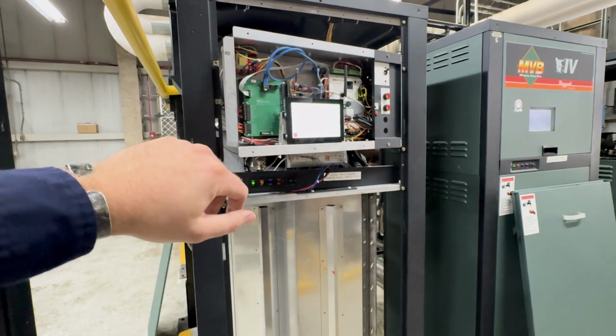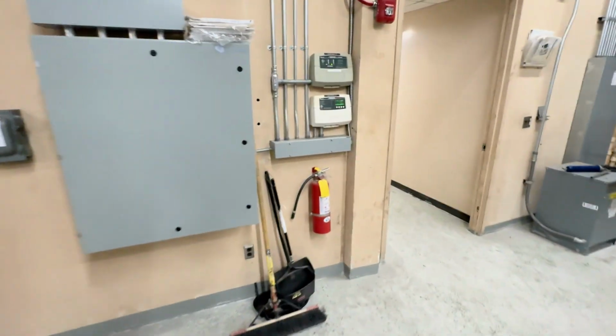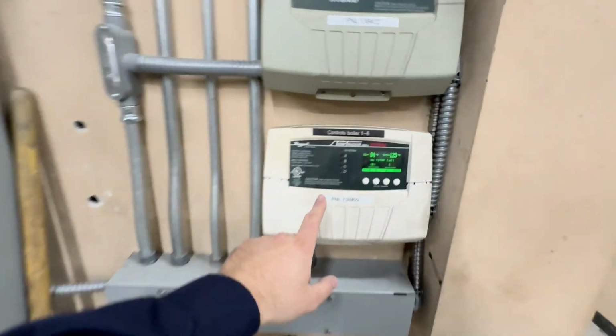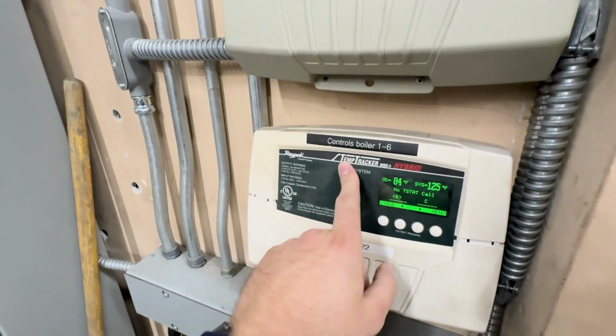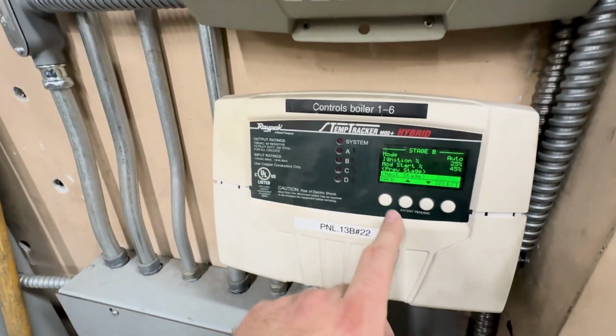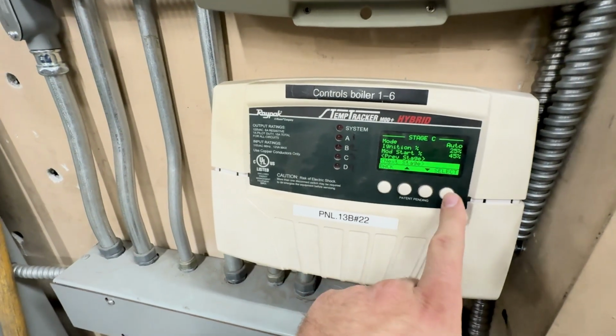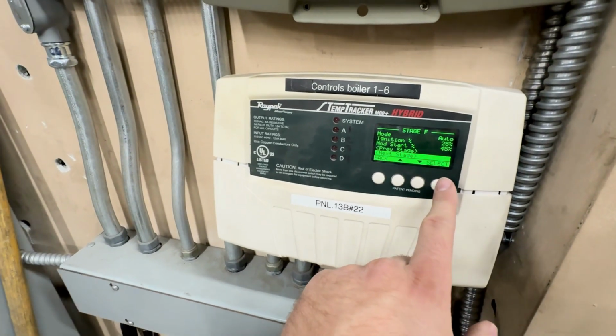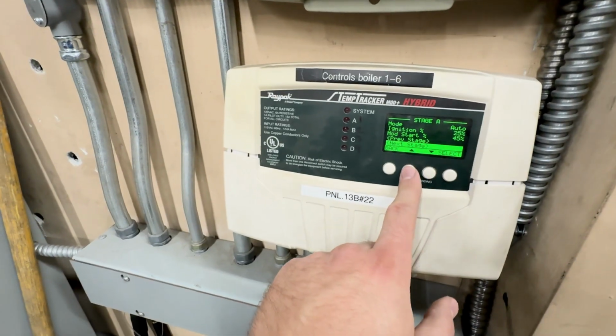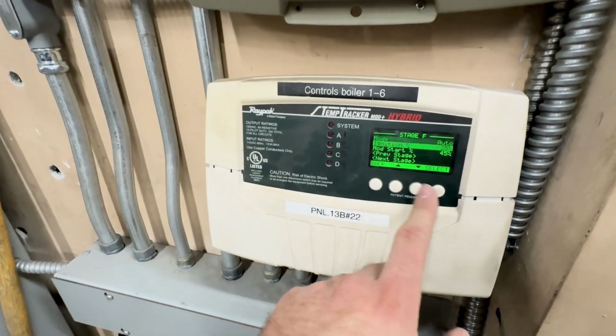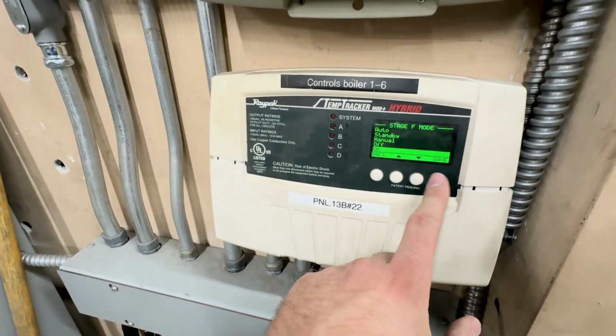Before we do anything else, we're going to keep the boiler on and we're going to go to the controller over here. Now these HVAC heating boilers are controlled by this Raypak TempTracker. We're going to go ahead and turn the stage on. That should be stage F. Mode on. So when you set it to mode on here, it's going to kick the boiler on to 100%.